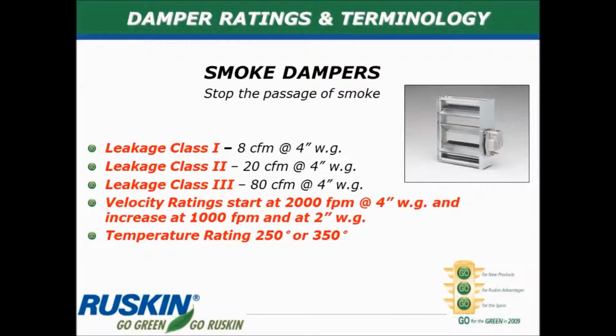Let's talk a little bit about smoke dampers. Smoke dampers are designed to block the passage of smoke, and there are various leakage classes that the dampers are rated for. Leakage class 1 is the best, and that will allow only 8 CFM of air to pass by at 4 inches of pressure, which is a fair amount of pressure. And then there's leakage class 2 and 3, which allow for more passage of smoke and air through there. I don't think I've ever seen a leakage class 3 damper specified, and by far most common we see leakage class 1, understandably. And it doesn't really cost much more to get those extra tight seals on the blades of those smoke dampers. So leakage class 1 is really the one you should always specify.